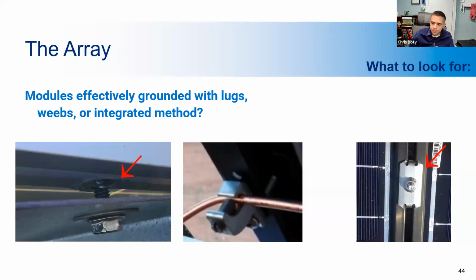So imagine you have a mason going on the roof to fix a chimney that's in disrepair, and he just touches the solar array, and he could be shocked with up to 600 volts of DC electricity, or potentially more, which would likely kill him. So you want to prevent that, obviously. And it can be prevented by careful grounding and bonding. A lot of systems nowadays have integrated bonding, which would be like this. It's kind of a clamp to hold the panels in place, and it provides a ground path through the system.